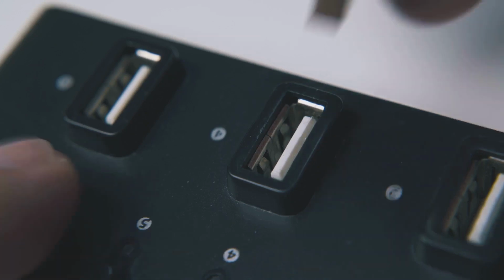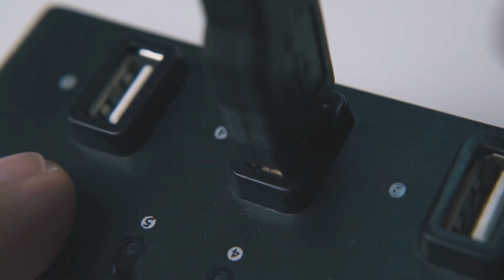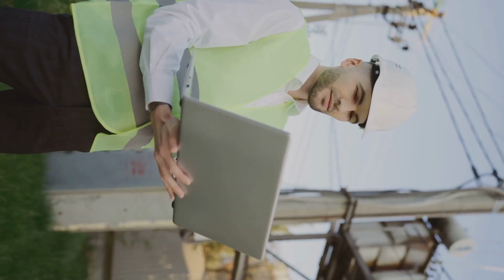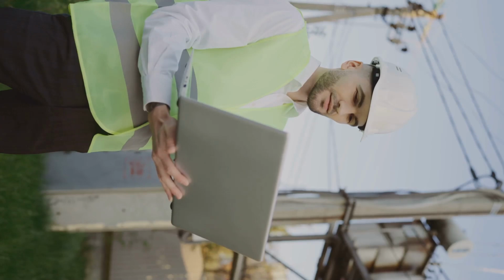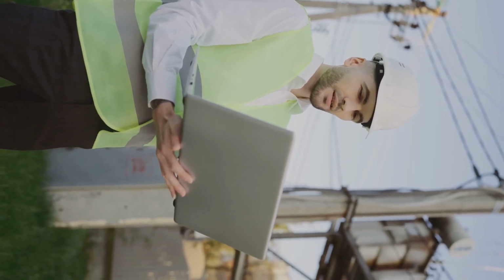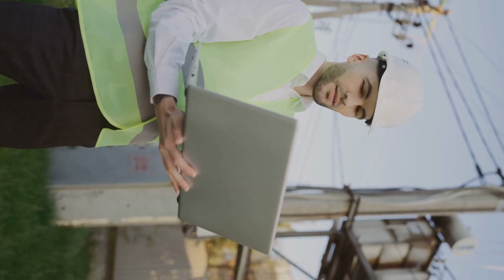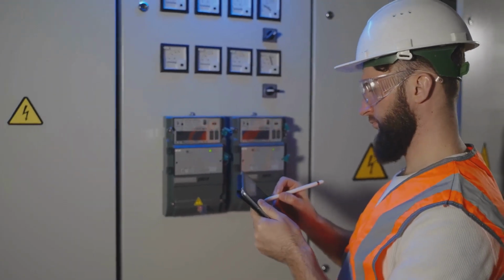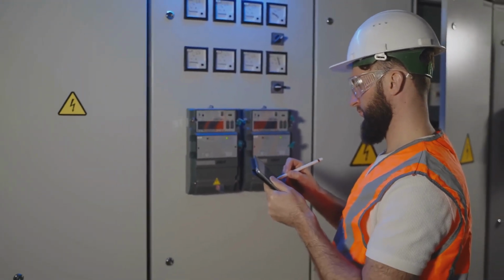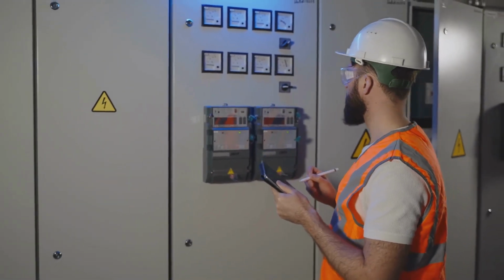Clause 4.10 Local interoperability interfaces. Even without wide-area communication infrastructure, DERs must provide local access, via USB, serial port, or Ethernet, to read and adjust settings. This allows field engineers to verify FRT parameters like voltage trip points, ramp rates, and reconnection logic.